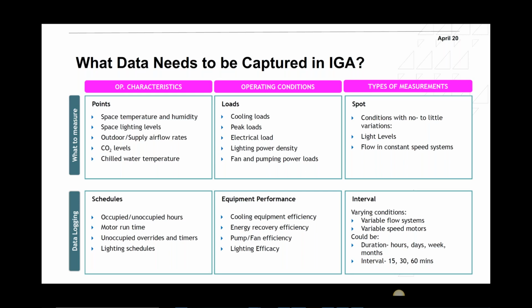Normally, I would put that for at least a month to see under different weather conditions what's happening. Energy recovery efficiency: if I have a fresh air handling unit or an outdoor air handling unit with a heat recovery wheel, I can take the temperatures before and after the wheel on the exhaust side and on the outside air side to see the energy recovery efficiency, compare it to the catalog value, and see how much it's doing, if it's worth changing or maybe cleaning it, and what the issue is with that particular heat recovery wheel and why it's not performing properly. It could be performing properly, and then it just assures us that it's working properly or not.